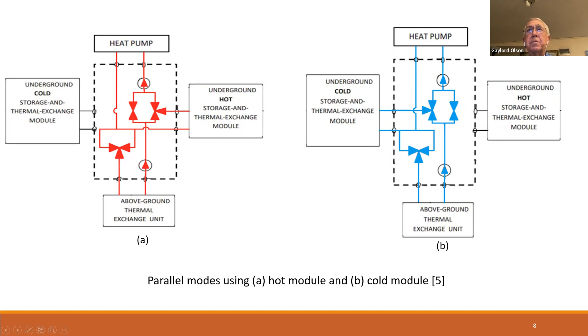So that parallel mode, oh, yeah, the parallel, oops, back up one. I skipped over something. Okay, this shows the parallel mode functionality of the system. When we have a similar temperature from the bottom block as we do from either the left or the right block, we can operate both of those pumps where the top pump is having twice the flow rate of the bottom pump approximately. And in that case, we'll get an equal flow from one of the underground blocks as compared to what's above ground. So we're calling this a parallel mode, and it gives a benefit in the transition range when the temperatures from two different sources are similar. And that shows up graphically on the next slide on the left. So advance one more, yeah.